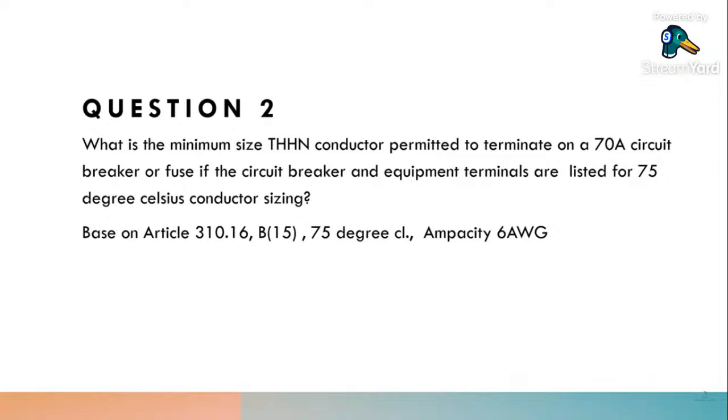Whenever you have a terminal, whatever conductor you terminate within that terminal should be of the same temperature rating or greater, or else the temperature rating of the terminal is going to take precedence over the temperature rating of the conductor.